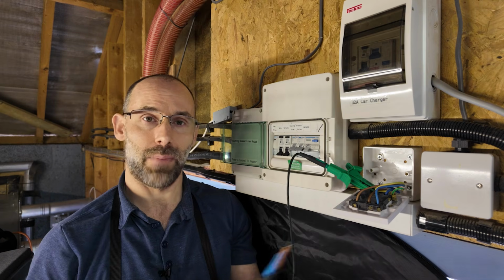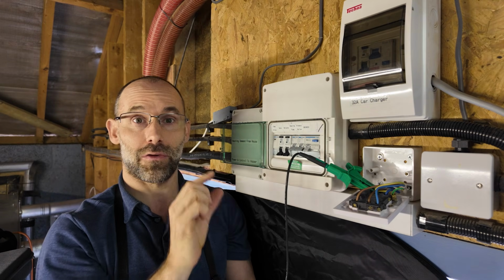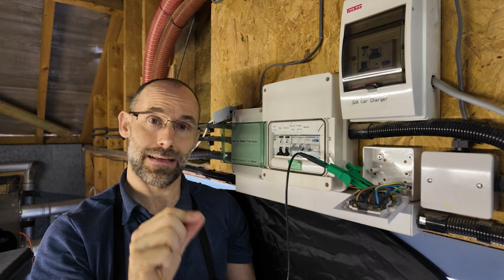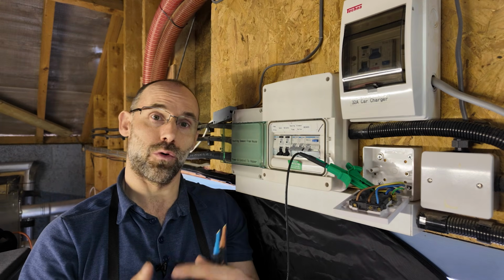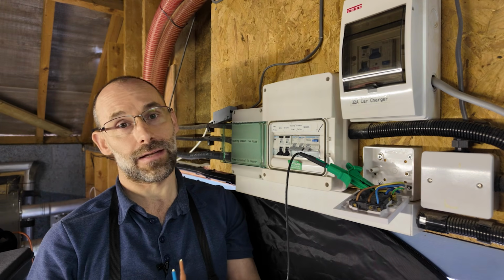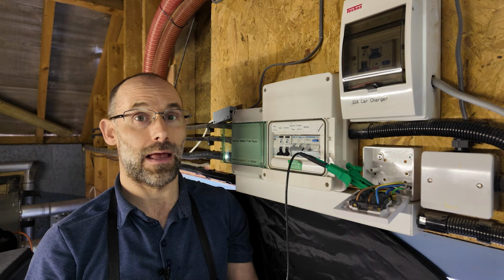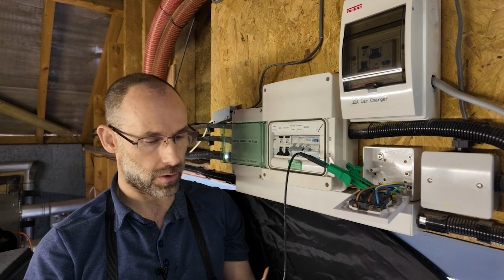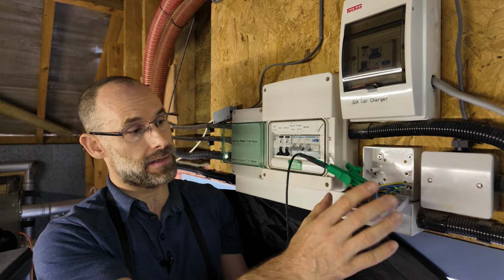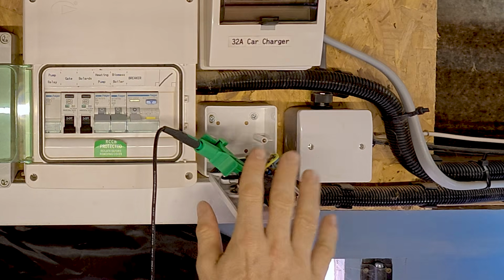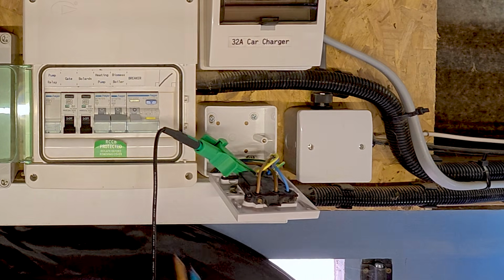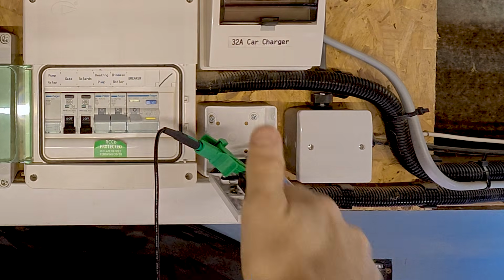That is a basic test, but we need to know more precisely that it's tripping at the right current: not too eagerly, which will cause nuisance tripping, and not too tardily, which would cause insufficient protection against electric shock. So when your electrician's doing this, they need to make sure they don't liven something like this with a front cover open when they're not present to protect it against you coming in and touching it. But in this case, I'm in control of this area.